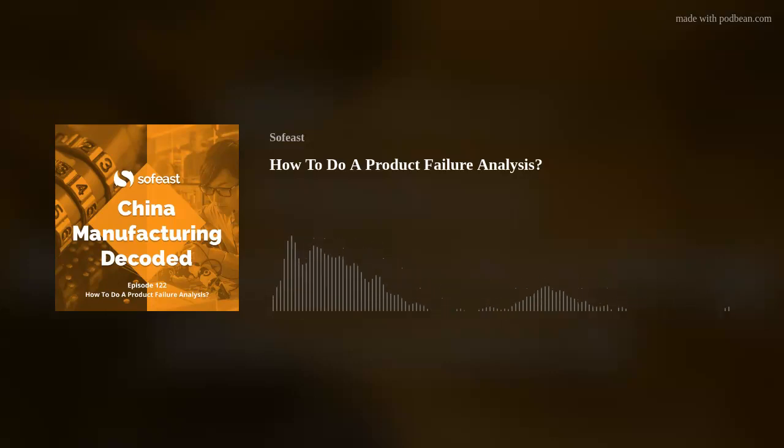If it's medical devices, no doubt, you have to analyze what happened, and you need to have a documented way to show that you really addressed that issue later, based on a very logical kind of problem-solving approach. Okay. And then hopefully the next prototype, you subject them to the same kind of testing to validate everything's fine and so on. Okay. That's during development.